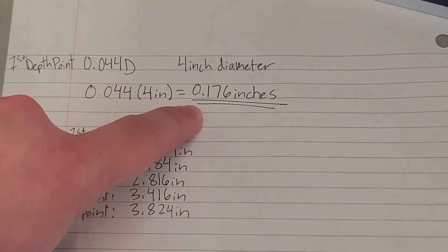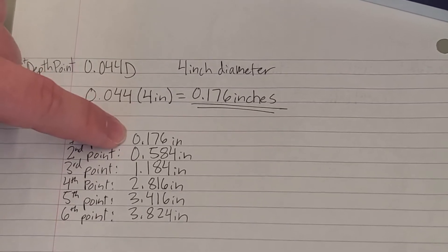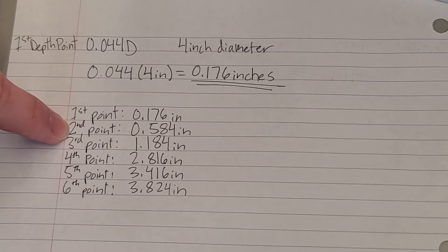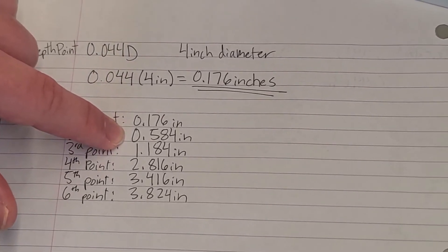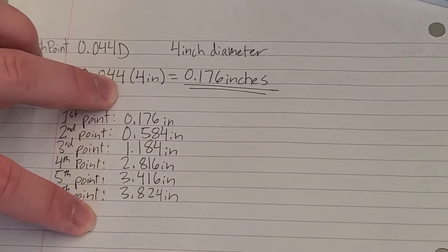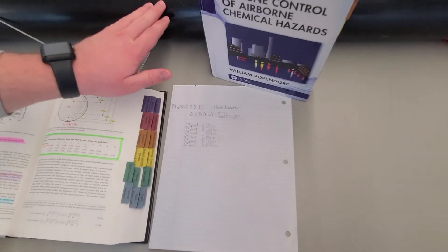We would then go down and calculate each point out individually. Starting at 0.176 inches, then we would take a second measurement at 0.584 inches and on down the list. We would take all of these points and measure them to make sure to get an accurate average air velocity across the whole duct.